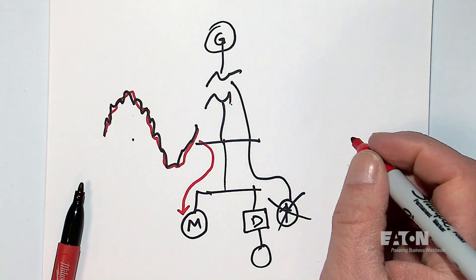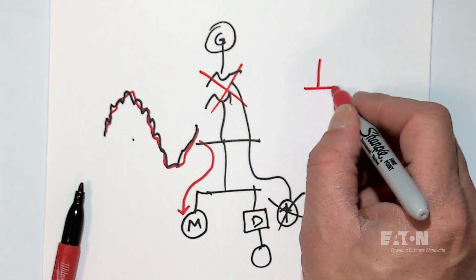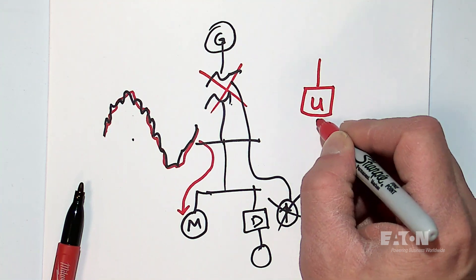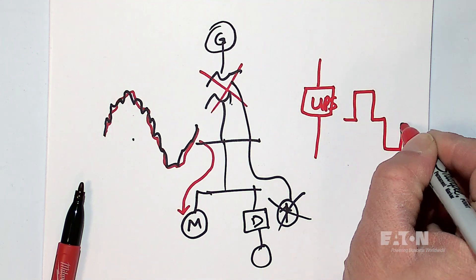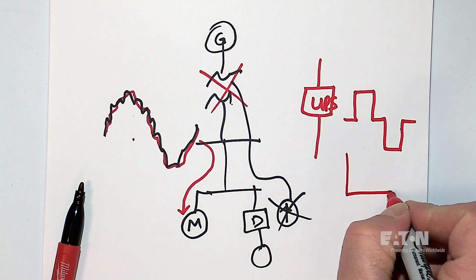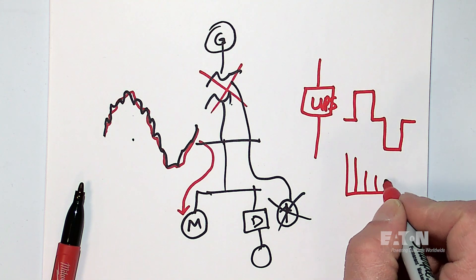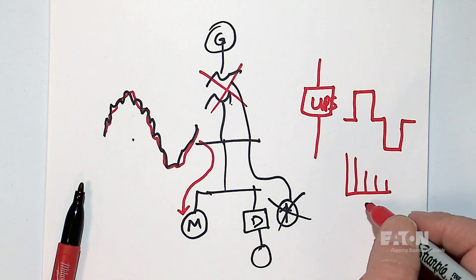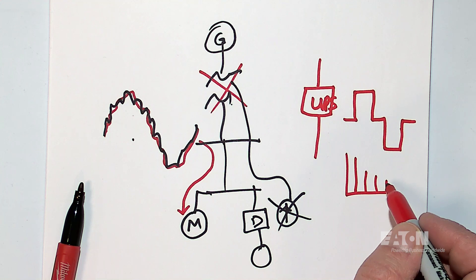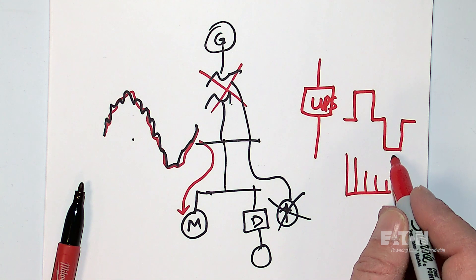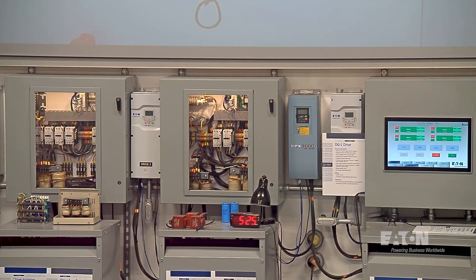A third example would be, let's ignore this here and put a UPS here, a small UPS that creates a square wave. Well, in fact, square wave voltage has fundamental voltage, but then it has a lot of the other frequencies associated with it. And for the same reason, loads downstream will draw a current that may look proportional to that voltage distortion. So at the end of the day...